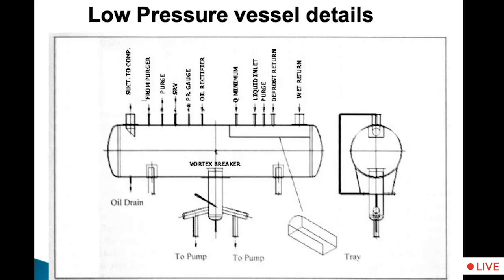These are the LP vessels. This is the LP vessel construction. There are important points. There is a liquid channel inside, if you see, where the returning liquid, the wet return, comes down, and there is a vortex breaker. Why a vortex breaker? Because even in your household applications, when your wash basin gets filled up with water, and you suddenly remove the stopper, you will find vortex formation. To avoid similar vortex formation, there is a vortex breaker, which is very essential. Otherwise, bubbles will be formed, and those bubbles will enter your ammonia pump, and your system will have a lot of problems. So this vortex breaker is important.